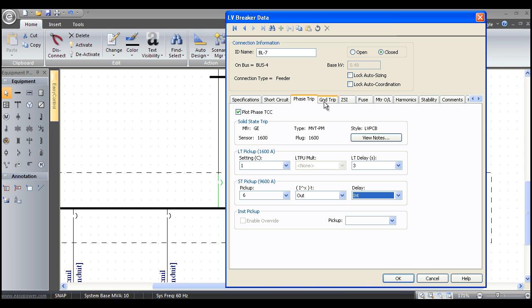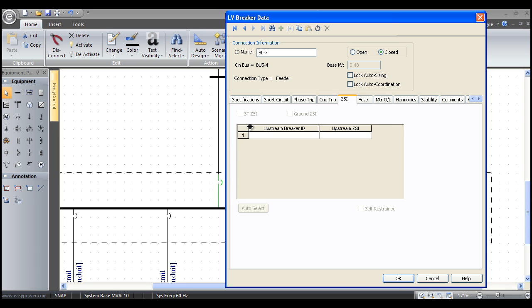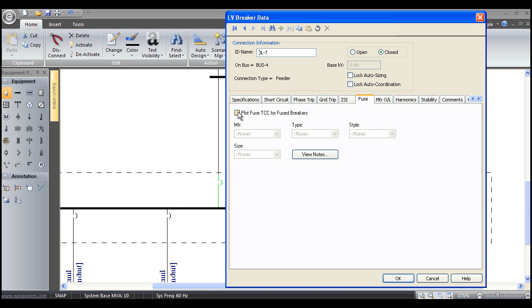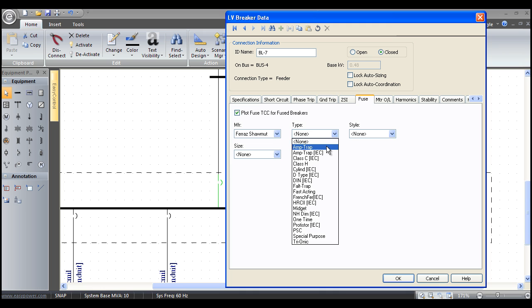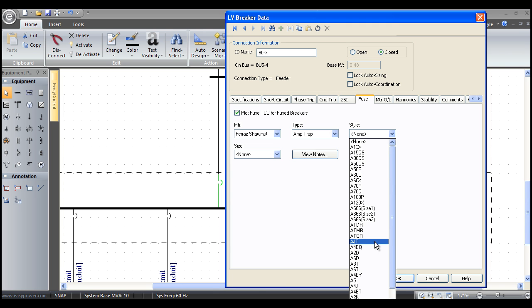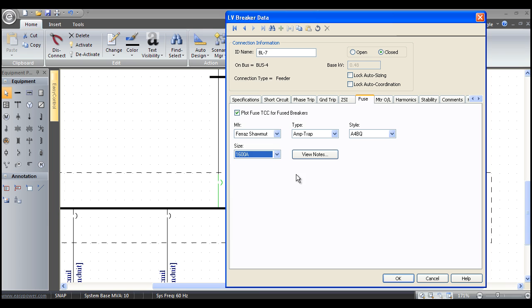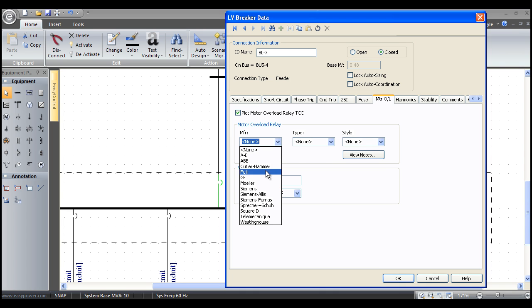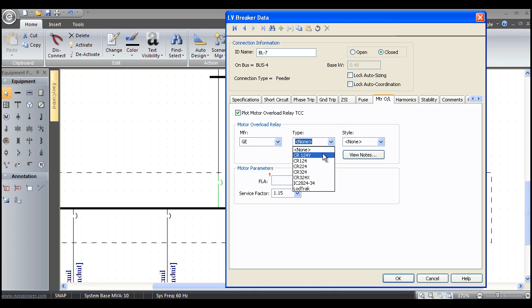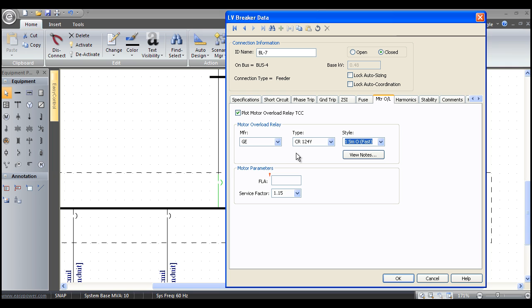If it has a ground trip, we just check plot ground TCC, and we can put in the trip device. If it had zone selective interlocking, we would just check the ZSI box, and we would put in our zone selective interlocking. If it has an integral fuse, such as an AKRU breaker, we'd check the fuse, tell it we want a Ferraz Shawmut Amp-Trap A4BQ, 1600 amp, and now it will integrate the fuse in all our arc flash and protective device calculations. Same with motor overload—if this was a molded case breaker and we had a GE CR124Y fast fuse, it would automatically integrate that with the motor circuit protector or thermal magnetic breaker.